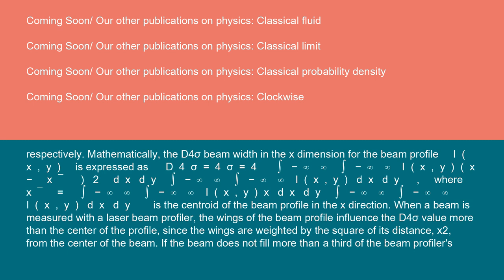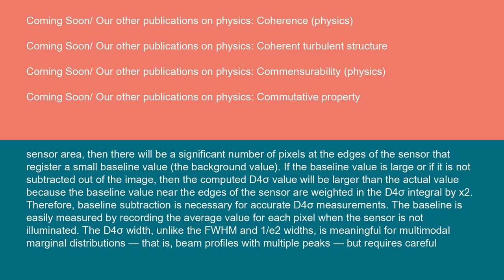When a beam is measured with a laser beam profiler, the wings of the beam profile influence the D4 sigma value more than the center of the profile, since the wings are weighted by the square of its distance, x², from the center of the beam. If the beam does not fill more than a third of the beam profiler's sensor area, then there will be a significant number of pixels at the edges of the sensor that register a small baseline value, the background value. If the baseline value is large or if it is not subtracted out of the image, then the computed D4 sigma value will be larger than the actual value because the baseline value near the edges of the sensor are weighted in the D4 sigma integral by x².